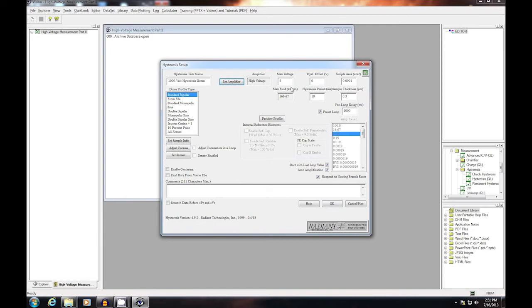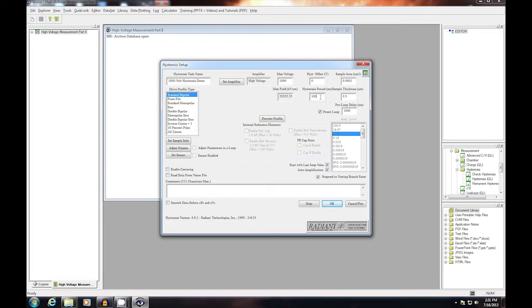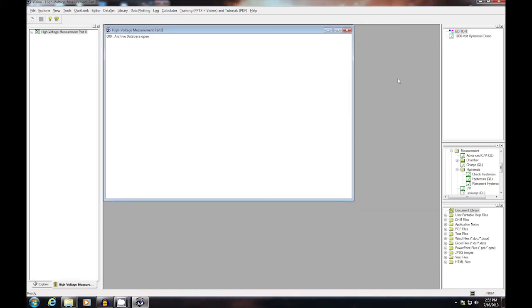Once I've selected the high voltage amplifier, I can now set 1,000 volts. I also need to make sure that I'm not exceeding the ramp rate of the external amplifier. So I'm going to go from a 10 millisecond to a 100 millisecond hysteresis period. Add appropriate comments. Then click OK to add the task to the editor.